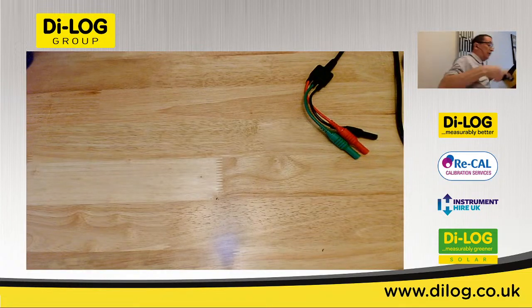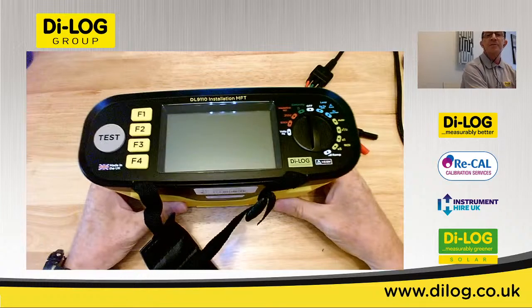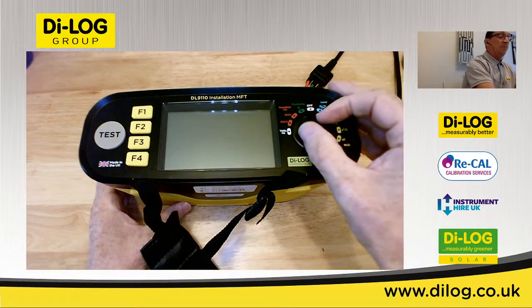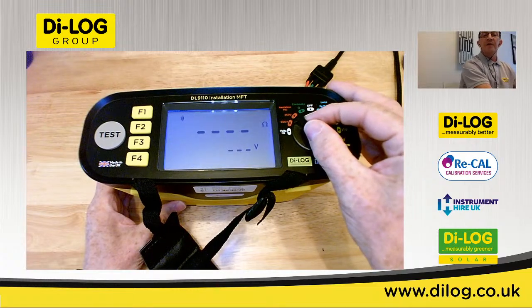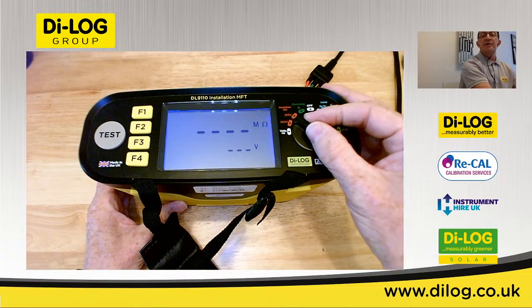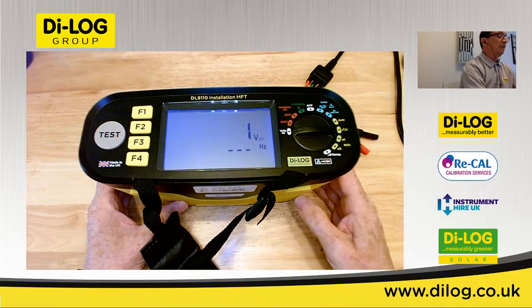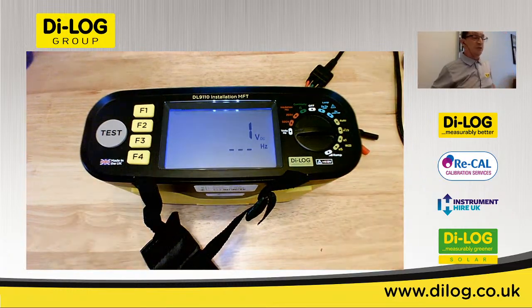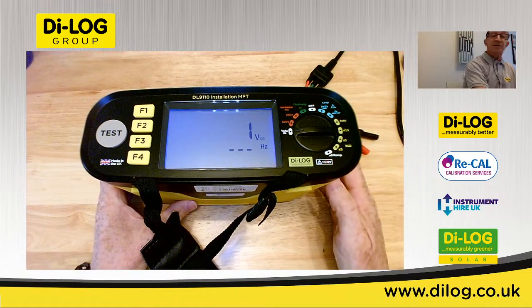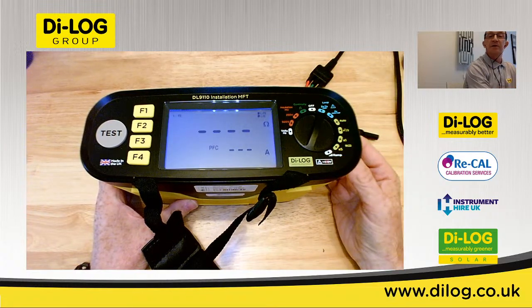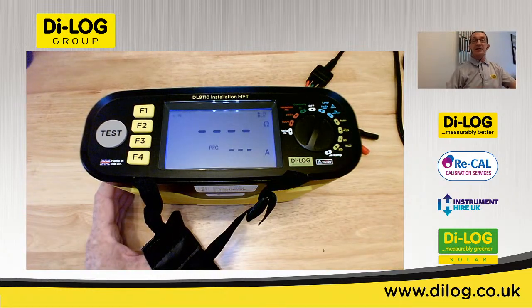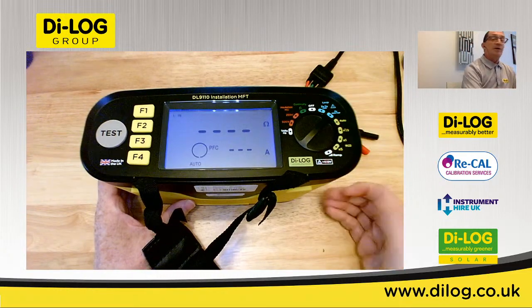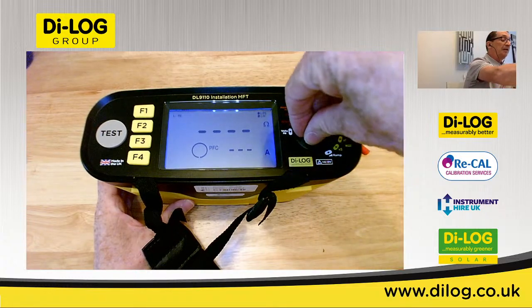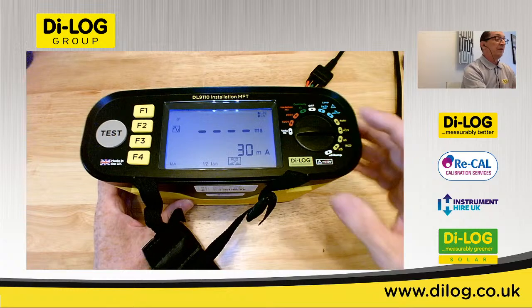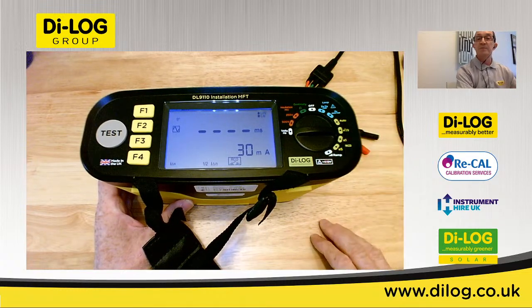Just bring the 9110 up just to show you the front panel of that one too. So here we can see the 9110, and we've got our continuity, we've got our 500 volt insulation resistance test, and the 250 volt. And also we've got the voltage and frequency on there. As we said, this model doesn't do phase rotation, so that final setting is limited to your voltage and frequency. But exactly the same, high current earth loop test, giving PFC and PSC at the same time, your no trip facility, and your fully functioning RCD section with auto test and with ramp test.